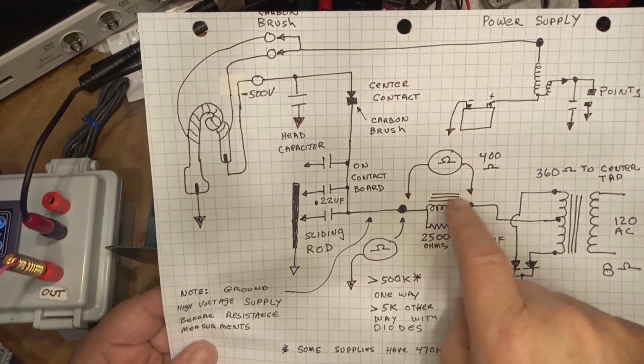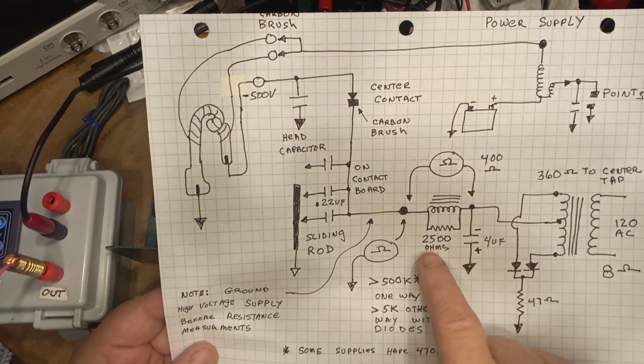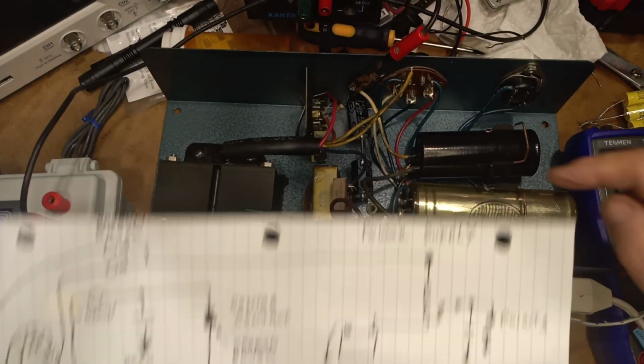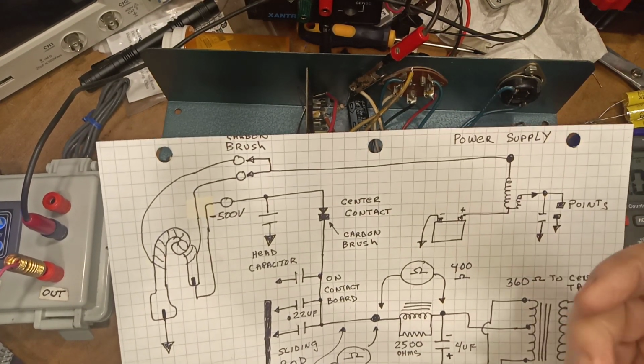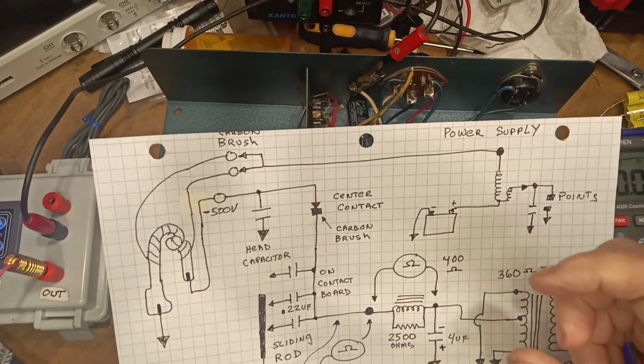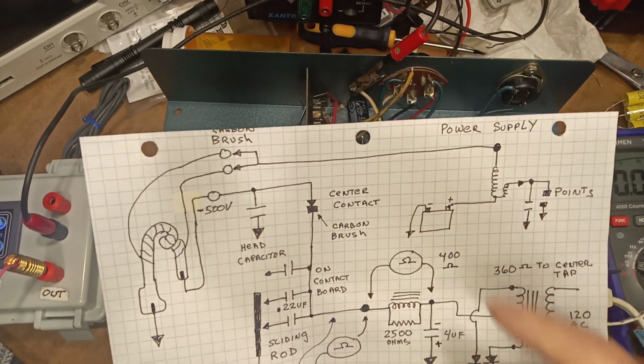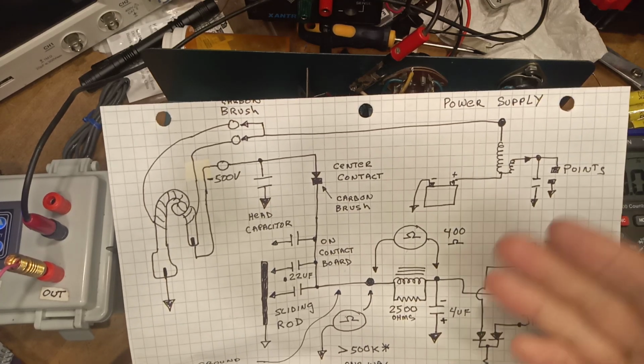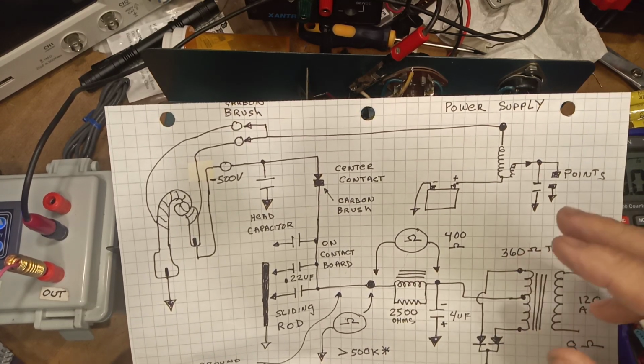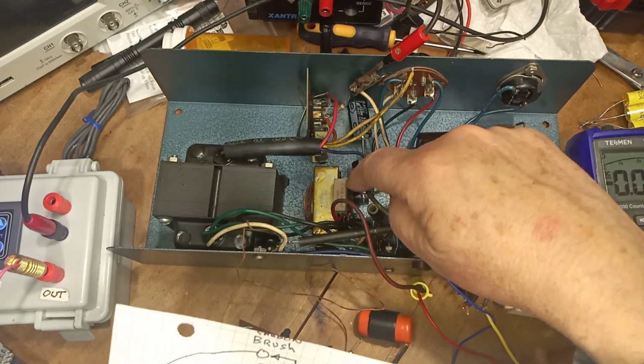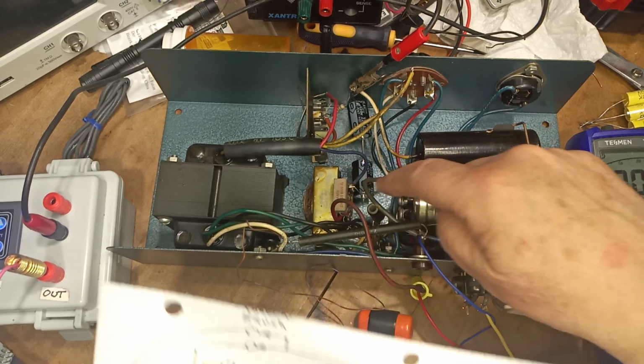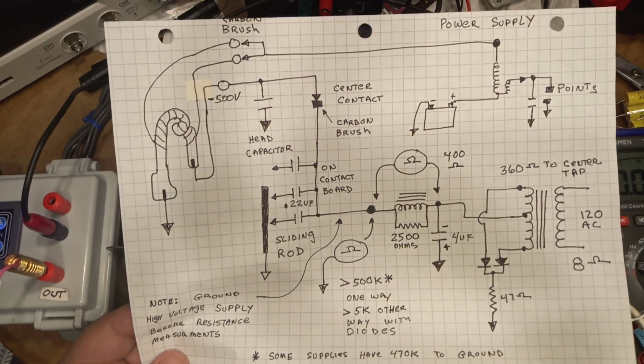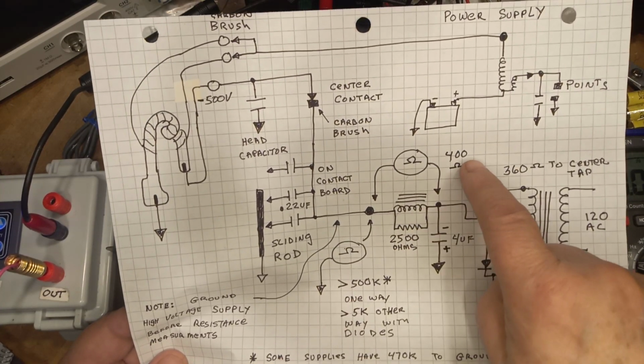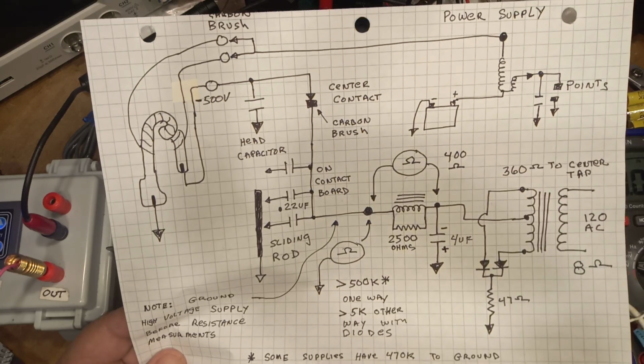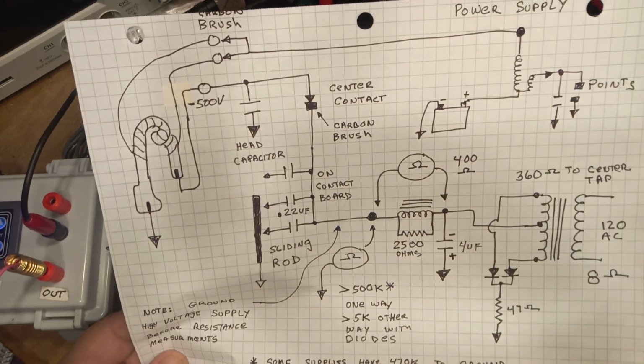But the coil resistance is about 400 ohms. They have a 2500 ohm resistor across it. Some of these coils get very old, and it's just metal connectors kind of snapped onto some cardboard, wrapped around paper, and if you put any force on this, you can easily break the wire, so be very careful with that. Across that coil, it should measure about 400 ohms. If it's way above that, you know you've damaged the coil and it won't work right.